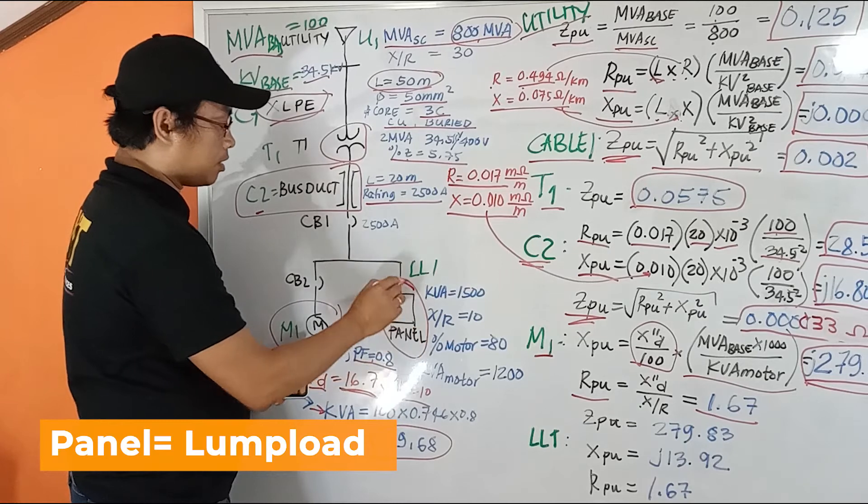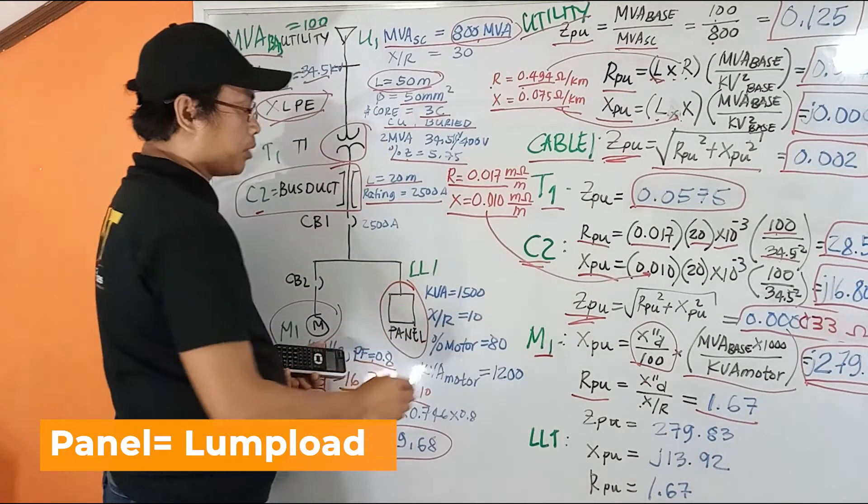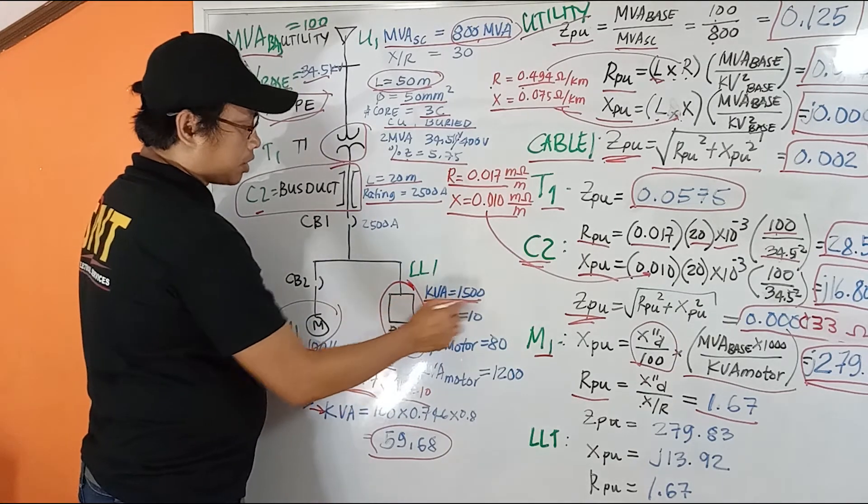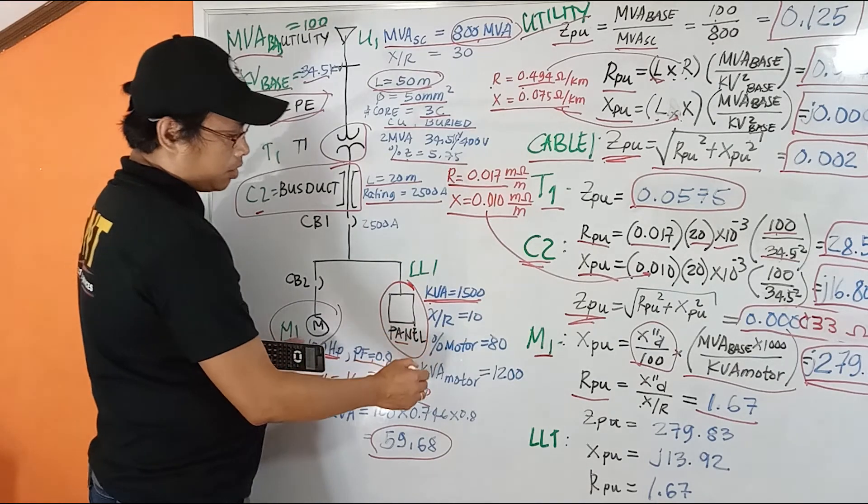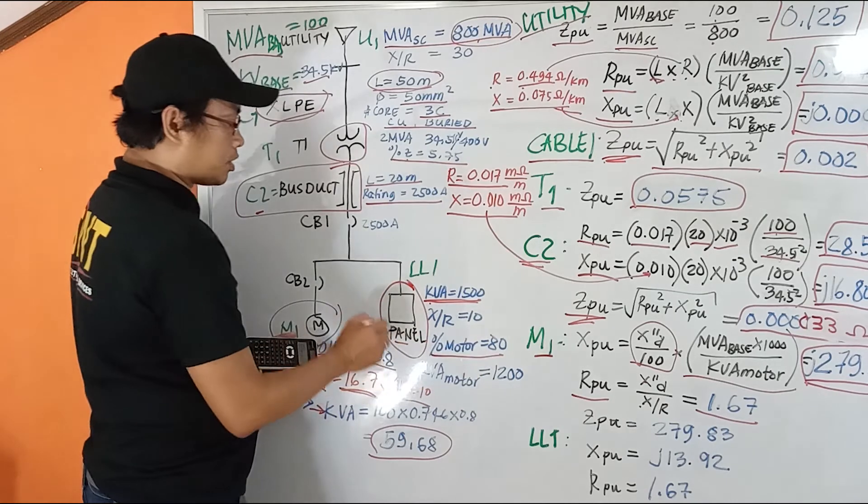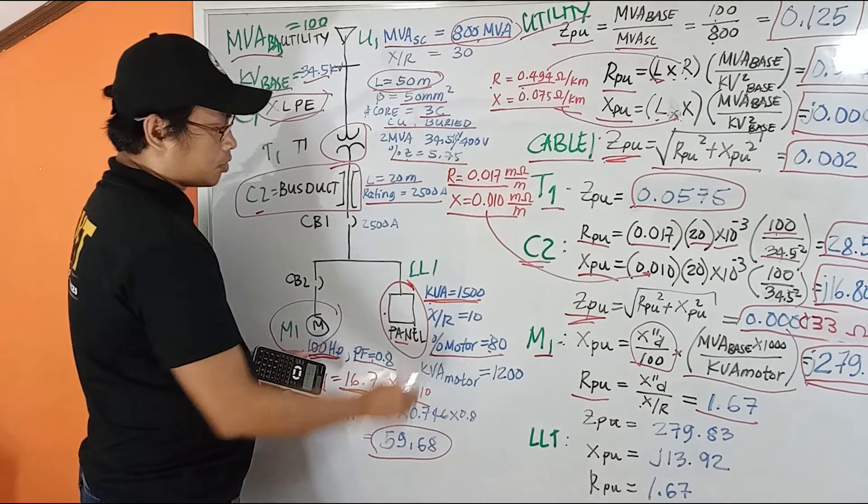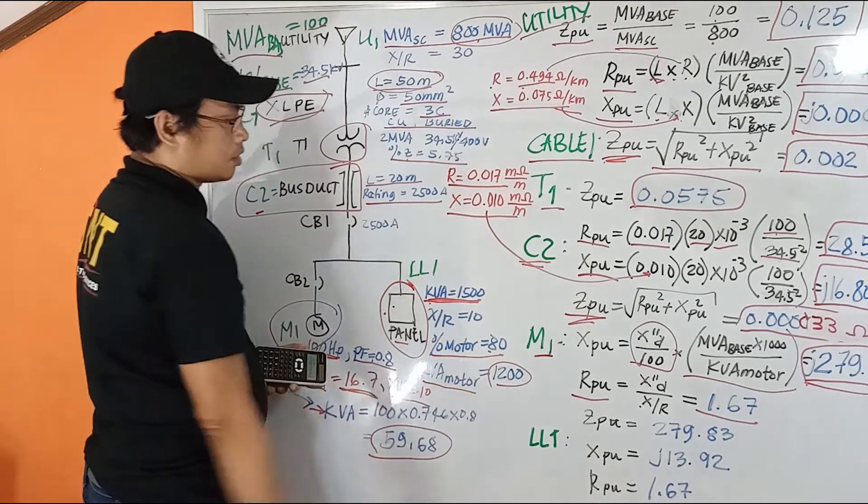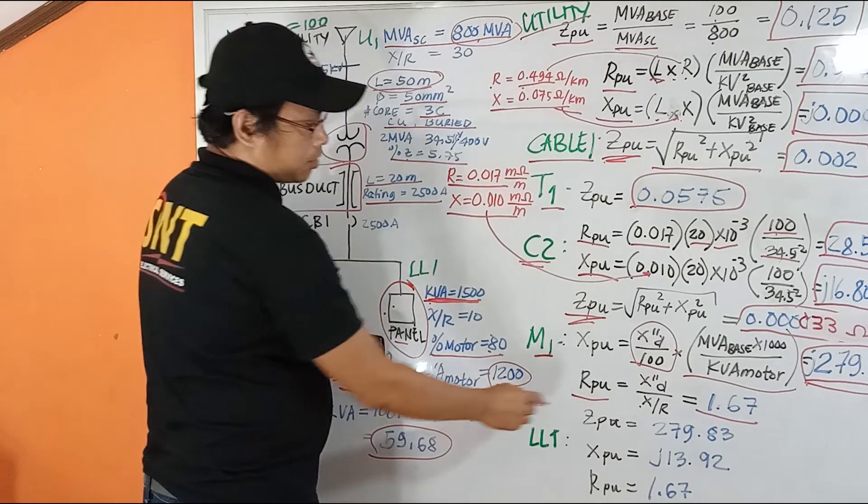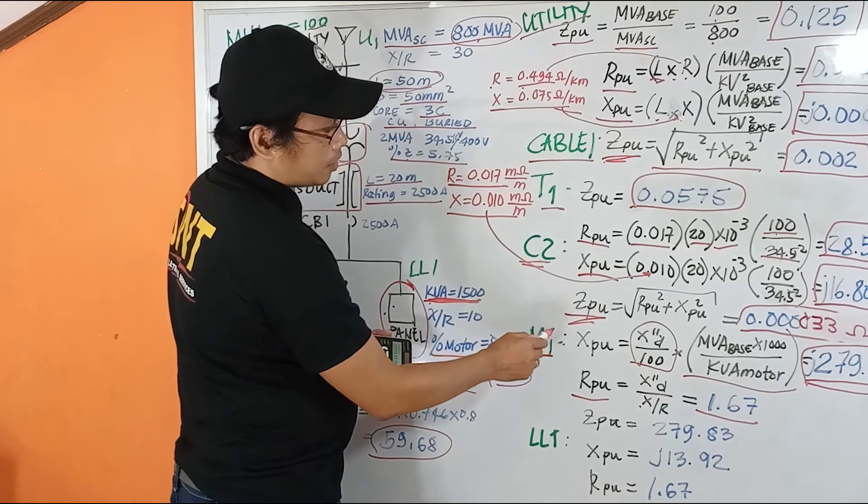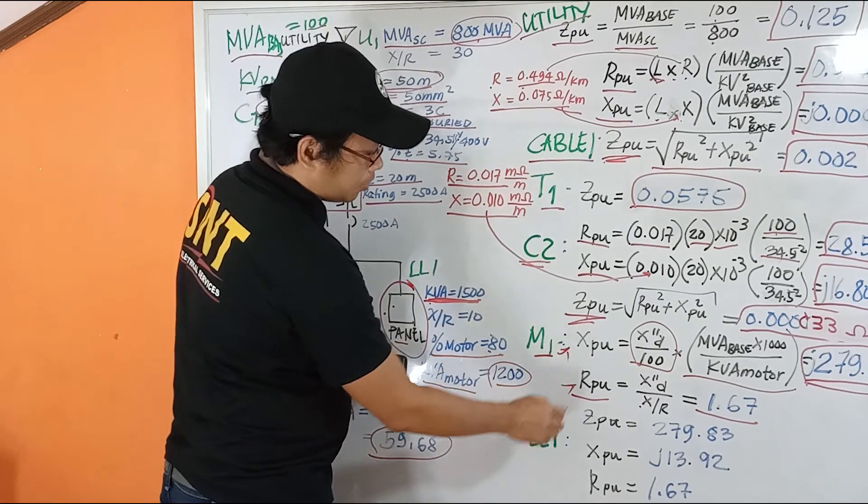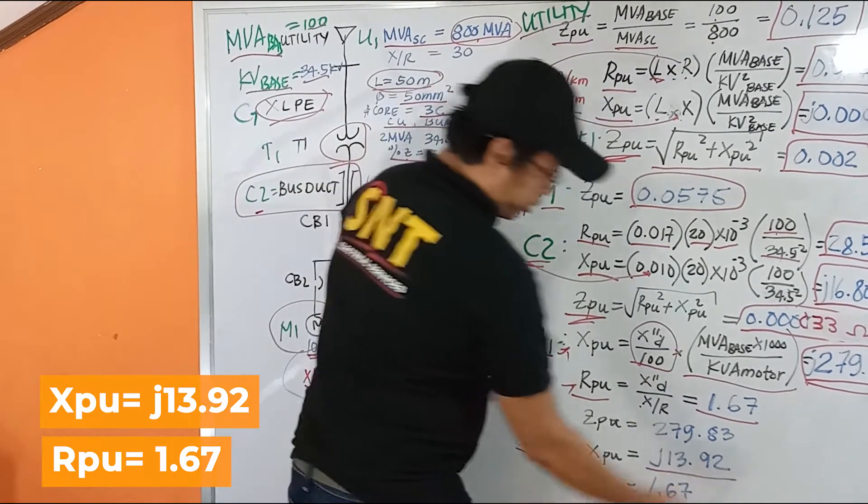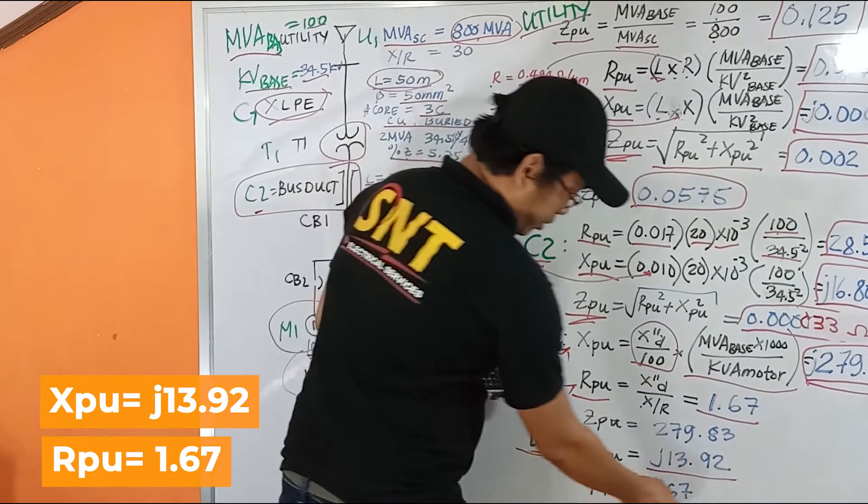Now, this panel is considered as lump load. So we calculate how much percent is motor for this panel. It was given the MVA of motor or percent motor on this panel load is 80%. So if this is the total load for this panel, you get the KVA motor at 1200 KVA. Then substitute it in our formula here, XPU and RPU for our lump load. We calculate that.